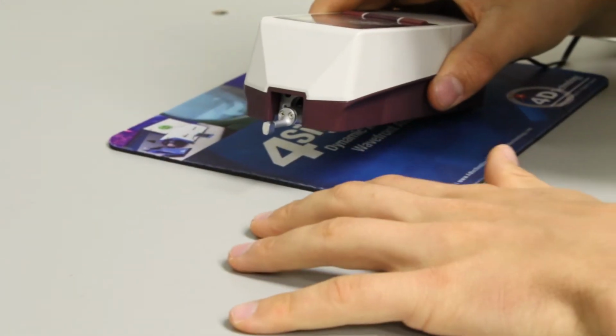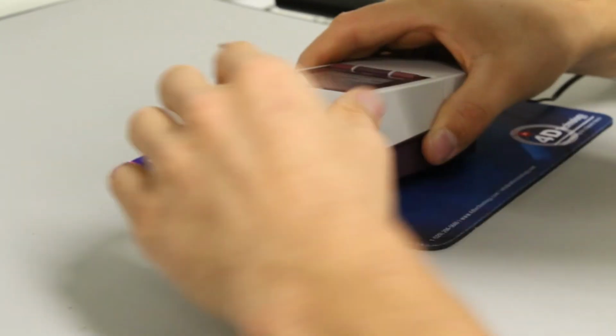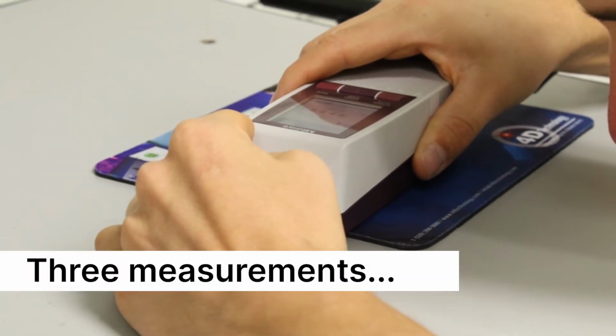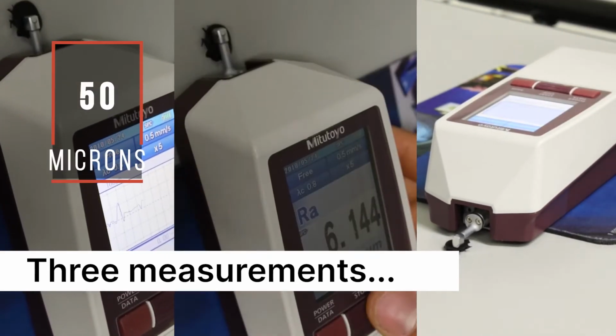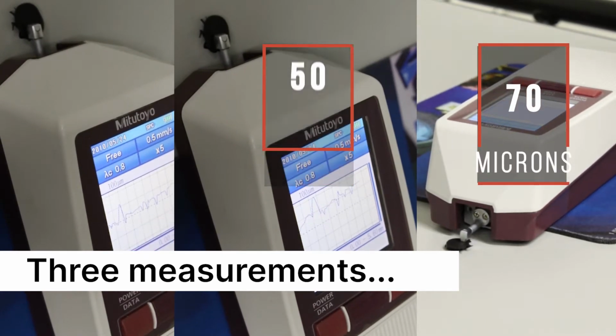Now I want to place it roughly on the high spot as far as I can tell. So I'm going to try to place it right there, and then push start. And that's around 50 microns. See that first peak. So that's again about 50 microns. So that was around 70 microns.